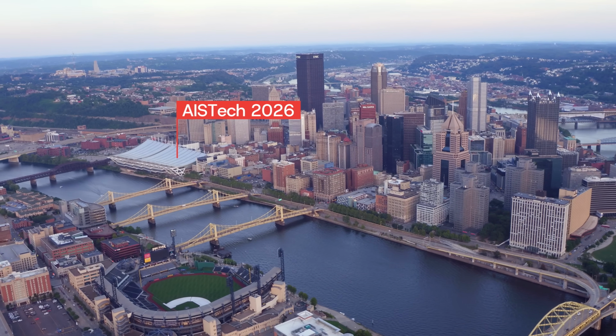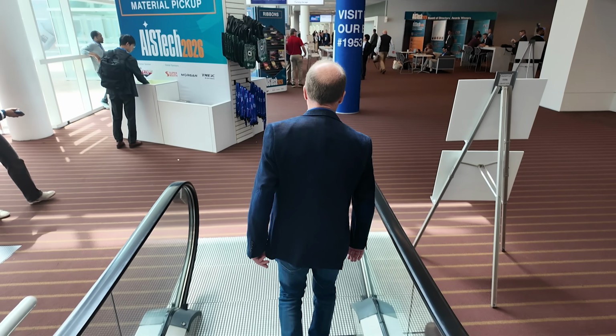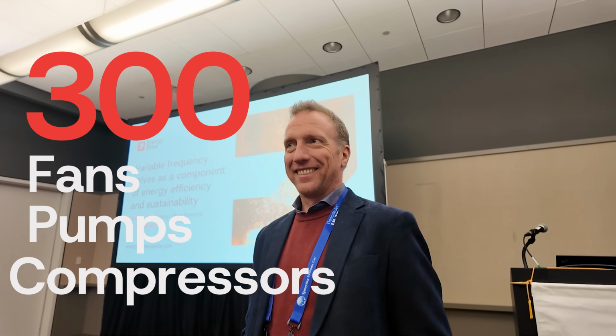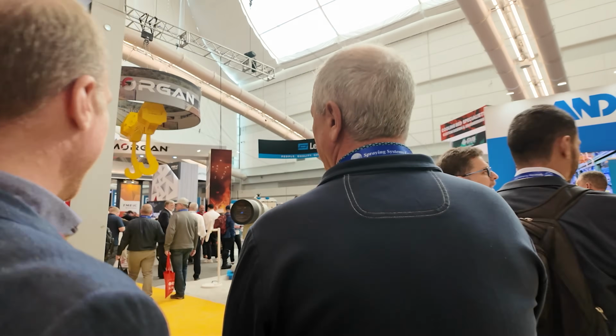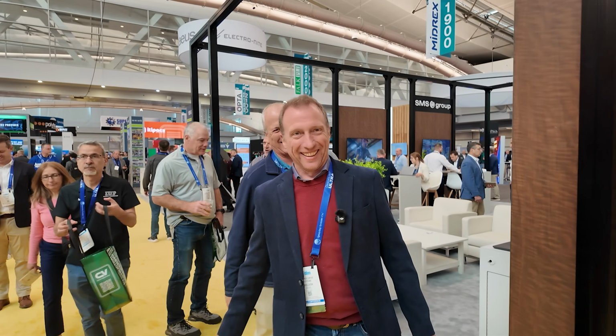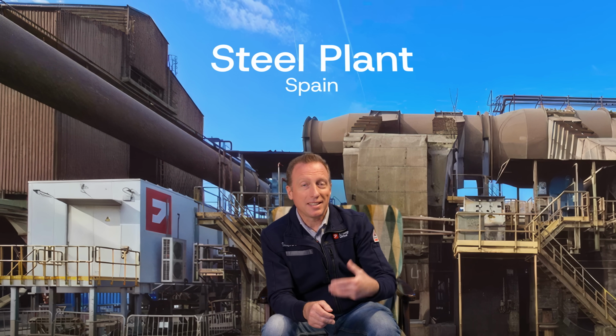This video follows on a talk that I did at AISTech in May, in which I unpacked 20 years experience working on fan, pump and compressed air systems, delivering energy savings between 30 and 80%. Our last system that we just commissioned is actually a fume extraction system on a steel plant that is delivering a consistent 60% energy reduction on 2 fans with VFDs. And for those of you like me who are into harmonics, we've got a couple of charts that'll unpack some of the fundamentals and some of the important principles about VFD installations.